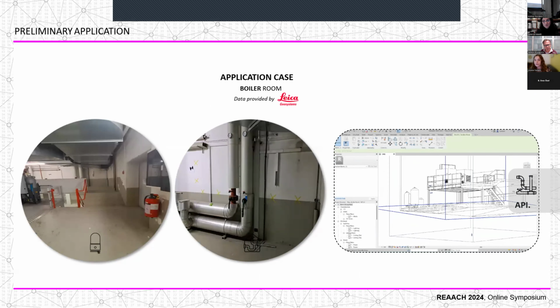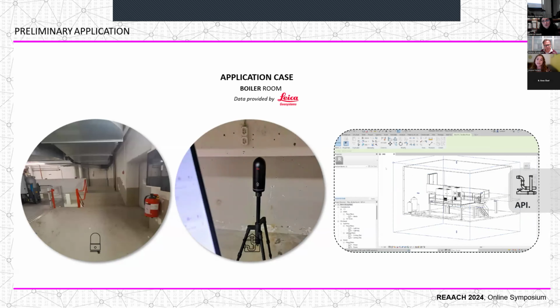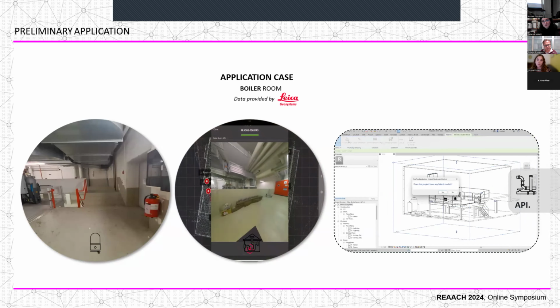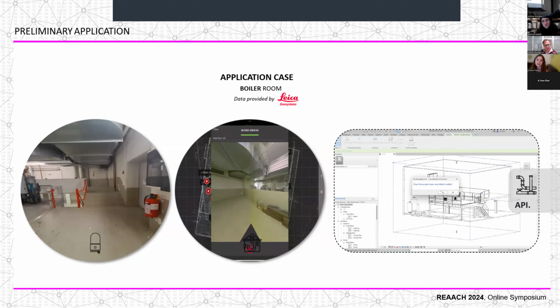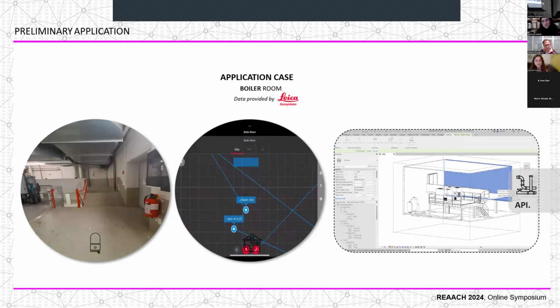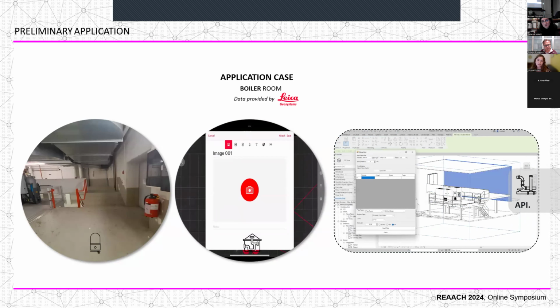Our wall detector was used to identify non-visible pipes within the wall. Through this detector, the points corresponding to the path and location of the pipes were marked and then converted into real tags using the Cyclone Field 360 application. Once the coordinates of the points were obtained, they were exported to the Create platform, facilitating the systematization of the processes and the creation of the pipe route.